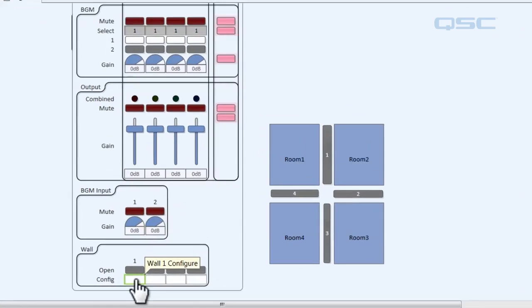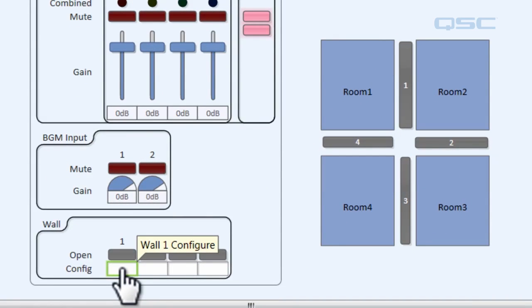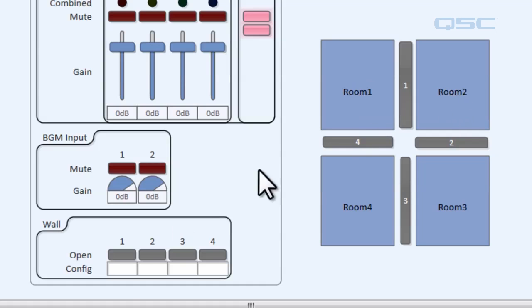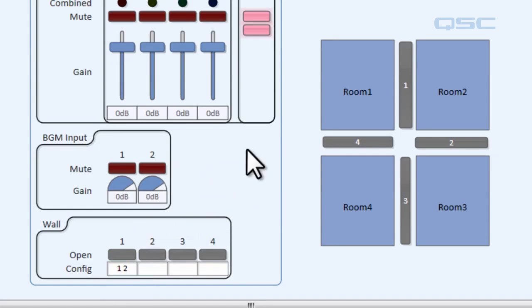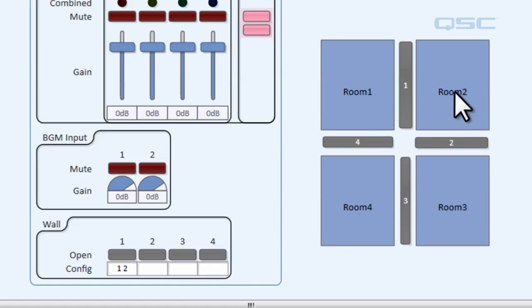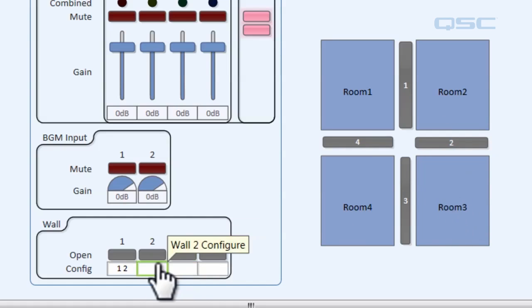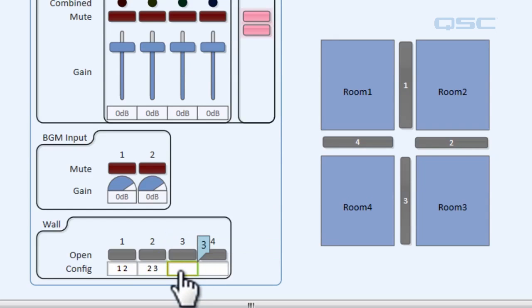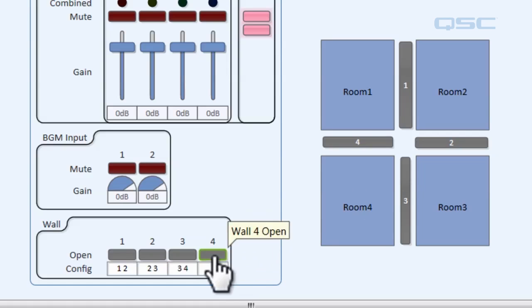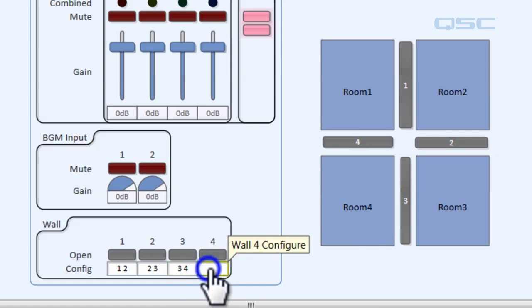Let's go ahead and do that by entering emulation mode. We come down to the config field — if we hover over it, it says 'wall one configure,' referring to the wall separating room one and room two. So we type '1 2' — make sure to put that space in there, it's really important. That tells the module room one is separated by a wall from room two. For wall two, between room two and room three, we type '2 3'. For wall three we type '3 4', and wall four, which separates room one and room four, we type '4 1'.